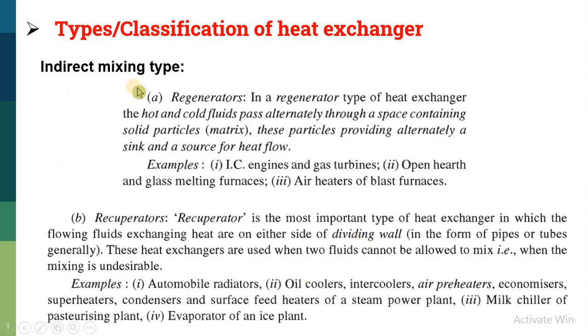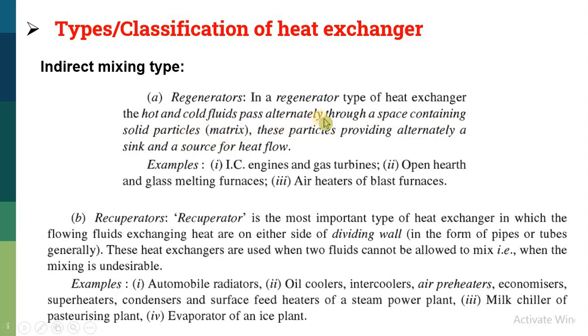Another type is known as indirect mixing. Unlike the direct type where hot and cold fluids mix directly, in indirect mixing the hot and cold fluids do not mix with each other. Number one is known as a regenerator. In a regenerator type of heat exchanger, hot and cold fluid pass alternatively through a space containing solid particles or a matrix. This means hot and cold fluid pass through the same passage but alternately, so they do not mix with each other.